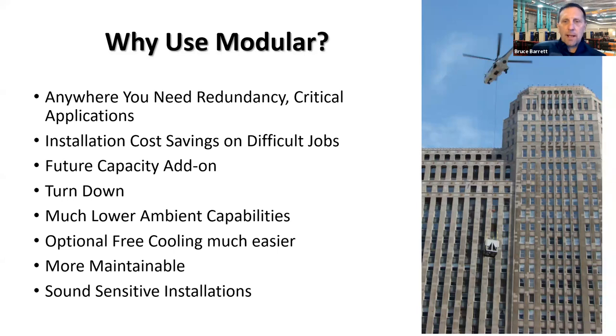We're going to talk about future capacity and add-on, and how easy it is with modular chillers. Turn down is a big deal versus a package chiller. I'll go into that more later. Much lower ambient capabilities, meaning 0 degrees is a typical standard low ambient condition. We can go all the way down to about minus 40, minus 50 with some accessories that we can place upon modular chillers. Our standard low ambient capability is minus 20. So that, you hope, covers 95% of the states.